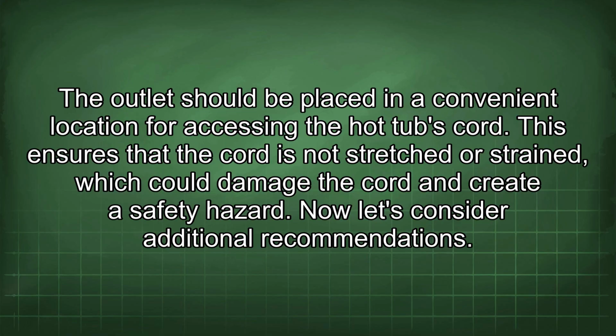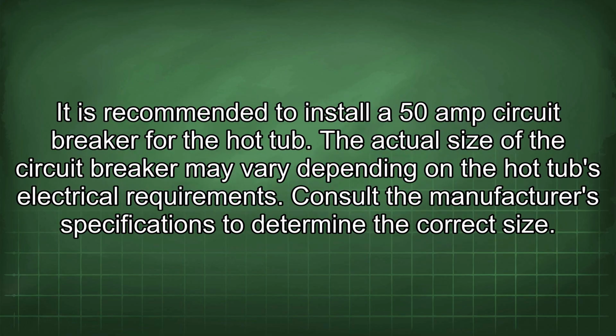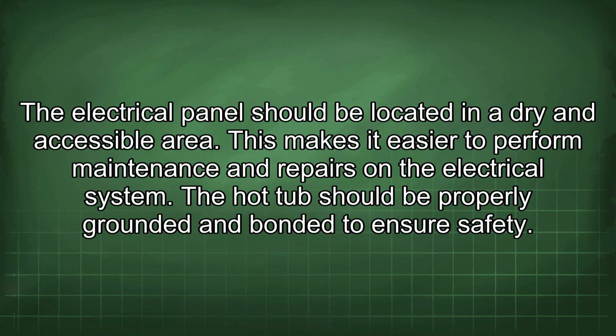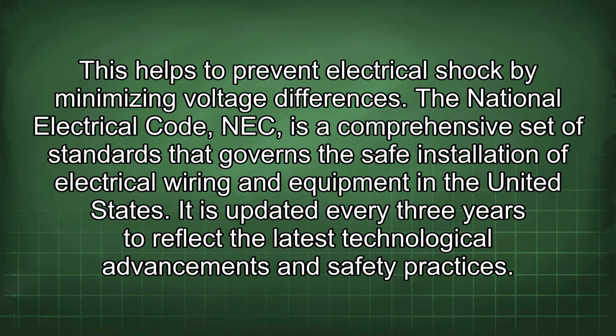Now let's consider additional recommendations. It is recommended to install a 50-amp circuit breaker for the hot tub. The actual size of the circuit breaker may vary depending on the hot tub's electrical requirements. Consult the manufacturer's specifications to determine the correct size. The electrical panel should be located in a dry and accessible area. This makes it easier to perform maintenance and repairs on the electrical system. The hot tub should be properly grounded and bonded to ensure safety. This helps to prevent electrical shock by minimizing voltage differences.